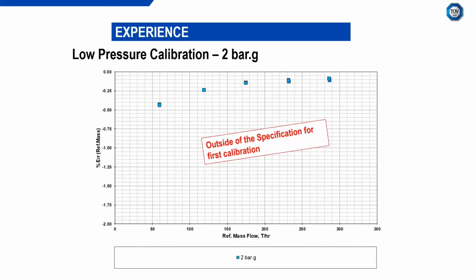However, the good thing about Coriolis meters is you can adjust them digitally without needing to change anything mechanically. You can change the mass factor, and we could adjust this meter, pulling up the performance so that it basically sat on the 0 line, apart from the lowest flow rates. You could apply a constant correction factor that would pull all the data up and make it well within 0.1% for the top 4 flow rates. So the mass factor could be easily adjusted. I didn't adjust it in this case because we're looking at research on uncorrected devices. We then followed up with some high pressure calibration points, which you're about to see.